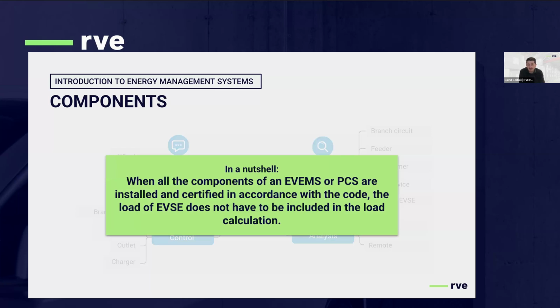In a nutshell, if we look at both the Canadian Electrical Code and the National Electrical Code in the US, if these systems are deployed correctly according to local jurisdiction, there will be some relaxation enabling you not to add the EV charger load to the load calculation. This is huge for how you deploy infrastructure, because it means you could completely offset EV loads if the system can manage the loads at all times without breaking the infrastructure.